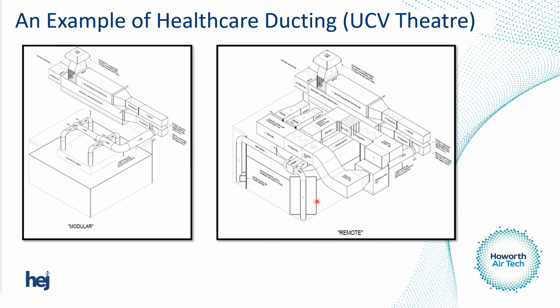Now, the other side of these remote systems here that you can see, they work in a similar fashion. The only difference is they don't have these fans that sit within the operating theatre. Usually it's taken from an air handling unit, and the fan does the recirc for the UCV. Now, an important point with these UCVs is the supply that comes from the air handling unit obviously gives the room pressure, gives the temperature control, the humidity control to the air, but it works in a recirculating fashion. So under the footprint of a UCV, you will have 500 air changes an hour. 33% of those air changes come from the ventilation system. 66% of the air changes come from the recirculating fashion of a UCV canopy. That's just the way that it works.